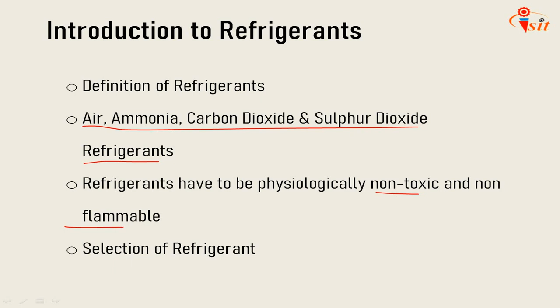The choice of a particular refrigerant depends upon the application in terms of refrigeration capacity, that may be categorized as very small, small, medium or large. Second, the type of compressor used, that may be reciprocating, rotary or centrifugal compressor. Third one, the refrigeration temperature required, whether for air conditioning, cold storage or food freezing. So that determines the choice of a particular refrigerant.